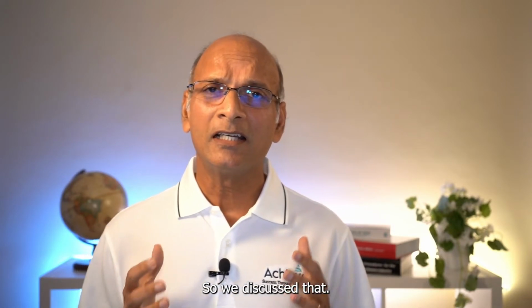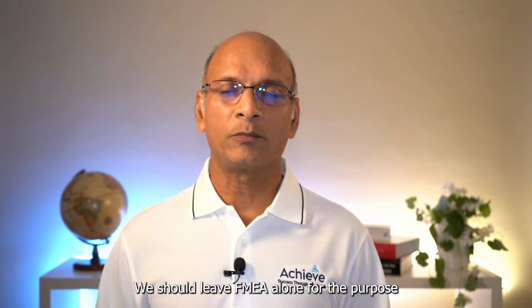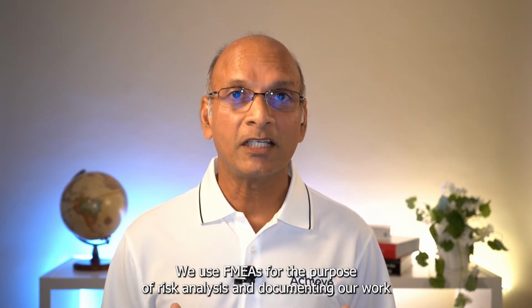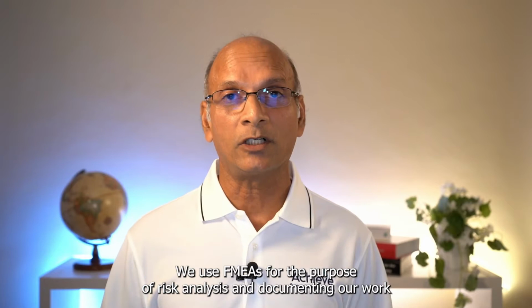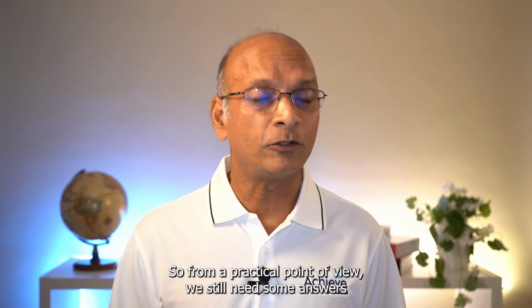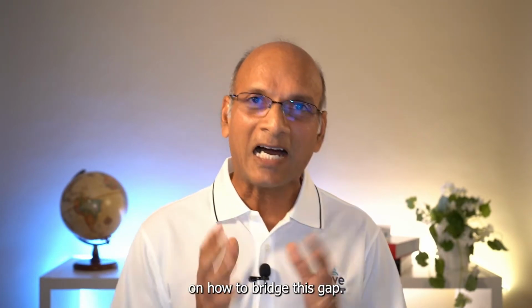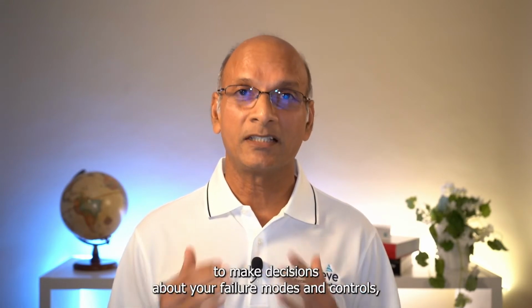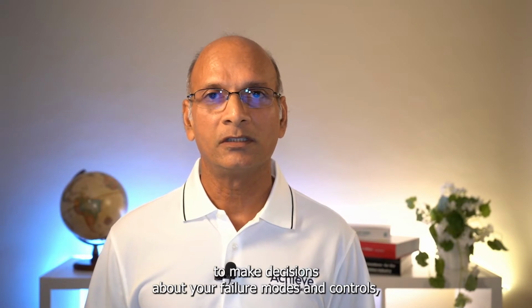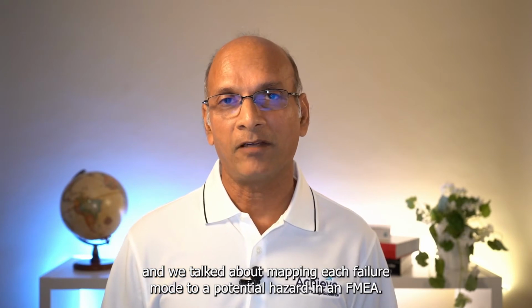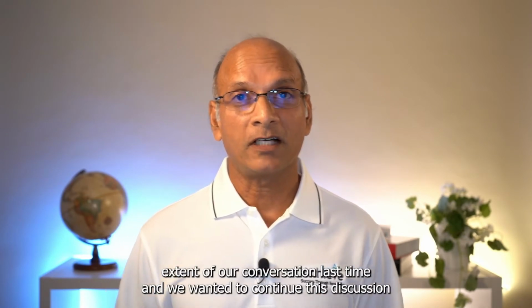So we discussed that we should leave FMEAs alone for the purpose of reliability and engineering failure analysis. However, I know that is not the practice in the industry. We use FMEAs for the purpose of risk analysis and documenting our work for ISO 14971 in a risk management file. So from a practical point of view, we still need some answers on how to bridge this gap. And we talked about using the RPN methodology to make decisions about your failure modes and controls. And we talked about mapping each failure mode to a potential hazard in an FMEA. That was the extent of our conversation last time.